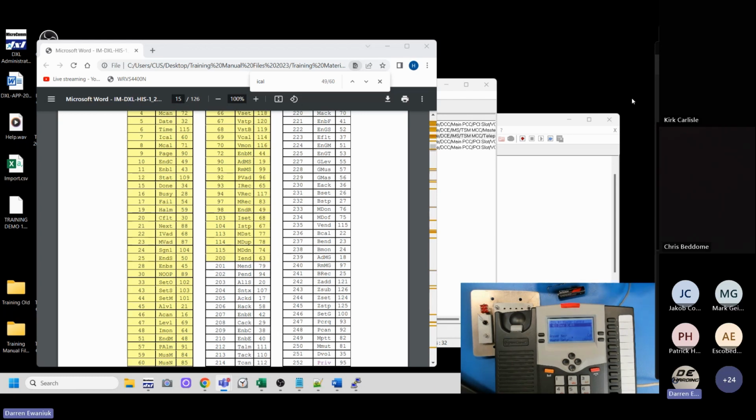The stat command is a really good way to make sure that your system can handle all messages. I mentioned previously that the intercom system will send, for example, a call request once. If you miss it, the intercom system thinks there's a call request, you think there's no call request, and there's a problem. It's not on the screen, so the staff isn't going to answer it. Now there's someone sitting at that door waiting for a response and nothing's happening, because it's in the intercom system, but it's not in your control system.